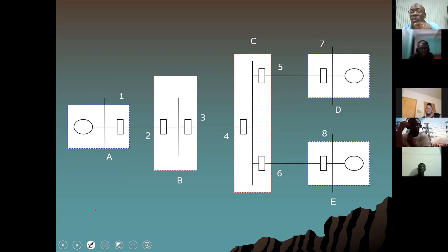So it is local, but which breaker or breakers are 4 and 5 backing up? Breaker 6. And breaker 6 is on the same bus bar with those that are backing it up. So in other words, it's in the same substation. That is why it is local. So it isn't about the line. It is about the fact that the backup breakers are within the same substation. We get the difference? Yes, sir. All right, good.